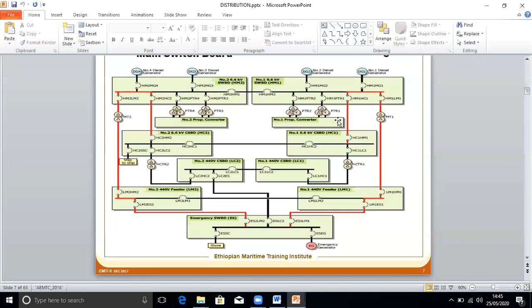And for generators, this is a high voltage switchboard. These are the transformers. What type of transformer is used here? This is a delta configuration. You see both of them are delta. Primary is also delta, secondary is also delta here. All of them are delta here. You see this also delta. Here you see delta star. So primary is delta, secondary is delta and star.